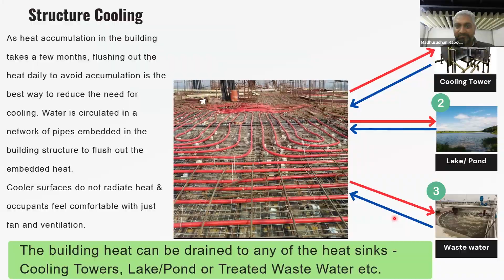So by the time April or May come, your space inside surface temperatures remain below 30 degrees centigrade, then at least in most part, you can get away with just fan and natural ventilation, which significantly brings down the cost of cooling. As many of you are probably aware, the biggest operating cost in air conditioning is the energy consumption by the compressor. If you are able to eliminate that, we achieve not just reduced energy consumption, but also not using refrigerant. In this case, it's just water.